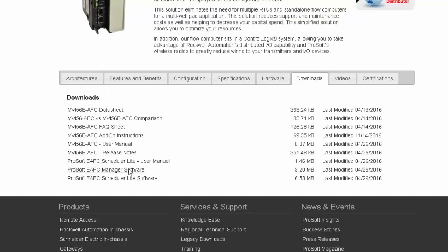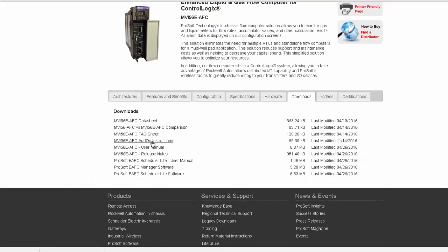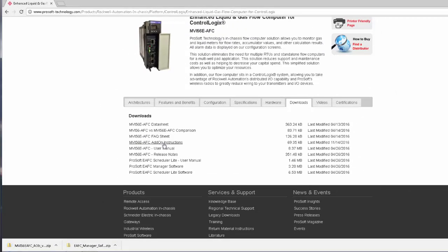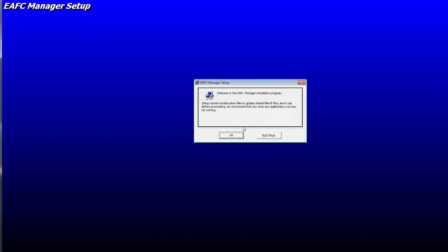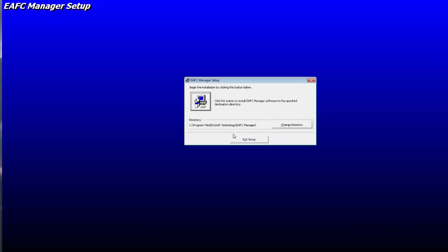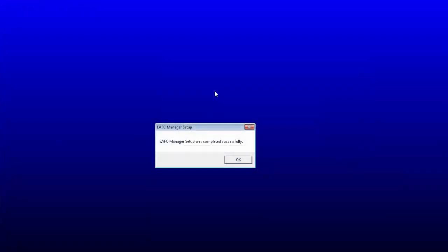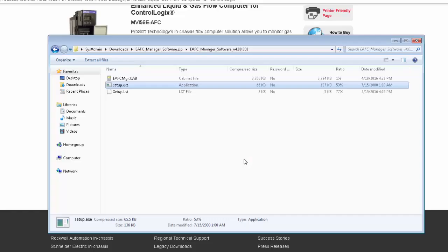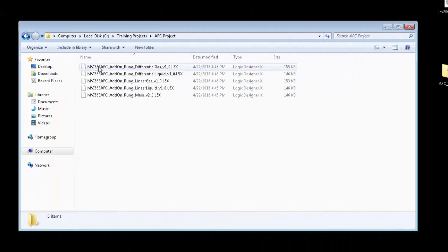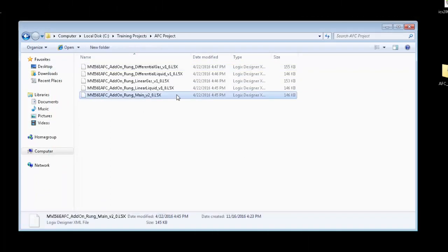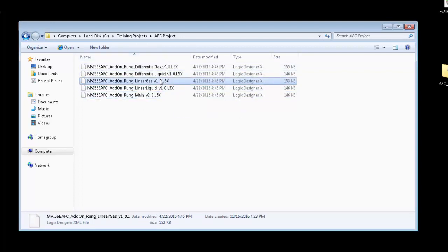And while we're on the product page for the AFC, we'll go ahead and grab the AOI file so that we can set up the module in our ControlLogix program. Once we have the files downloaded, go ahead and install the EAFC Manager to your PC by following the prompts. The AOI file we downloaded is a zipped folder that contains the main AOI as well as four additional AOIs, one for each of the main meter types.